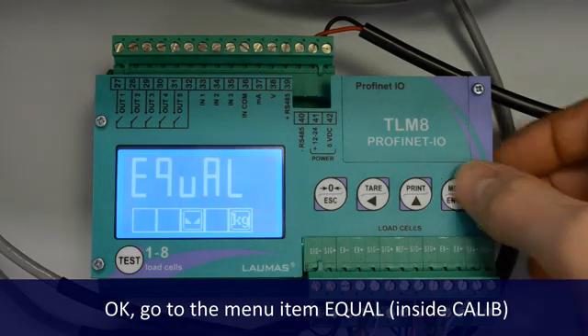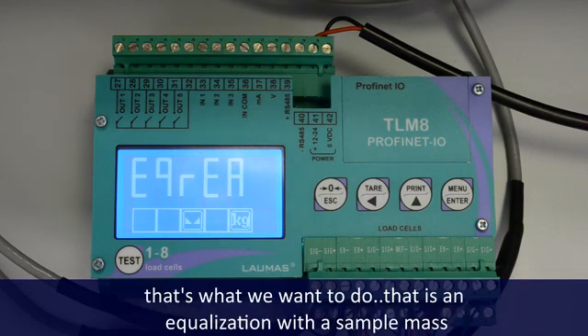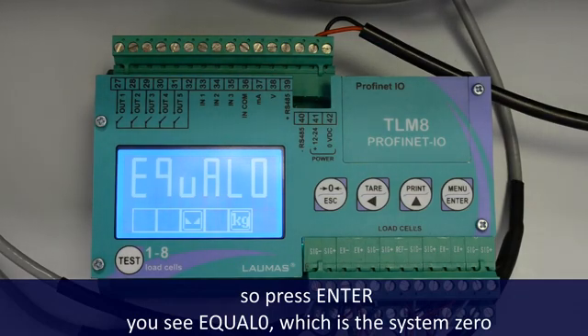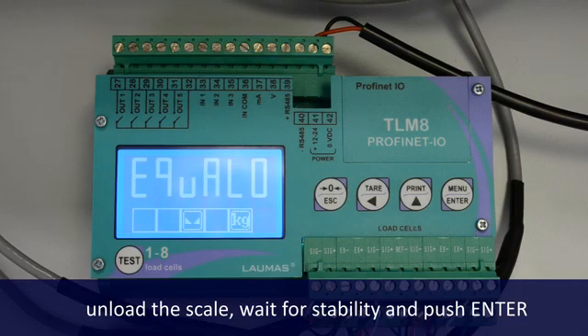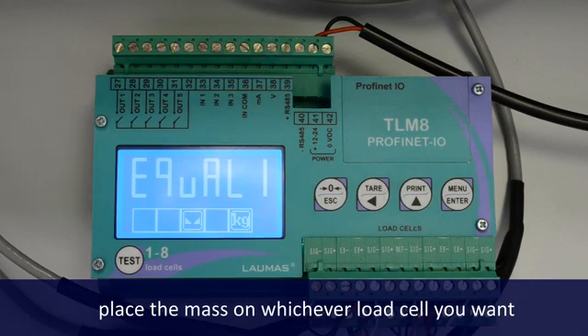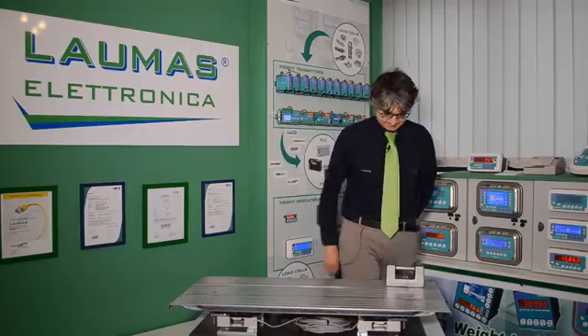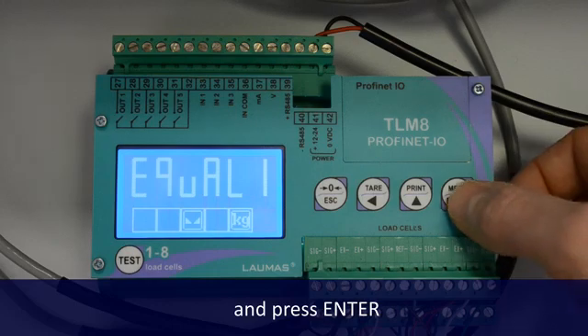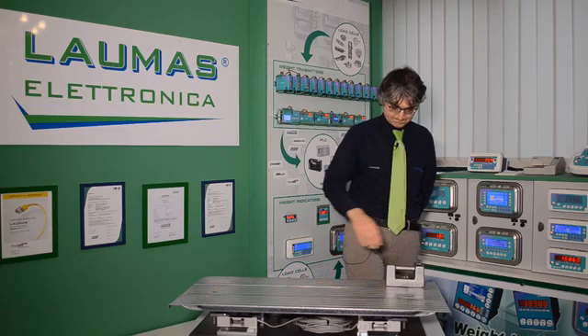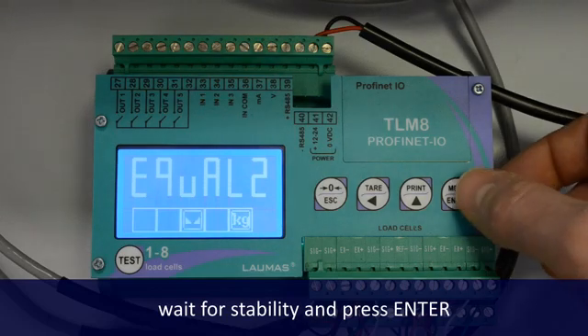On the menu page, you see EQUAL, which stands for real equalization — that is what we want to do, an equalization with the sample mass. Press Enter, you see Equal 0, which is the system zero. Unload the scale, wait for stability, and push Enter. You now see Equal 1. Place the mass on whichever load cell you want. Wait for stability and press Enter. Now you see Equal 2. Move the mass to the next load cell. Wait for stability and press Enter, and so on.